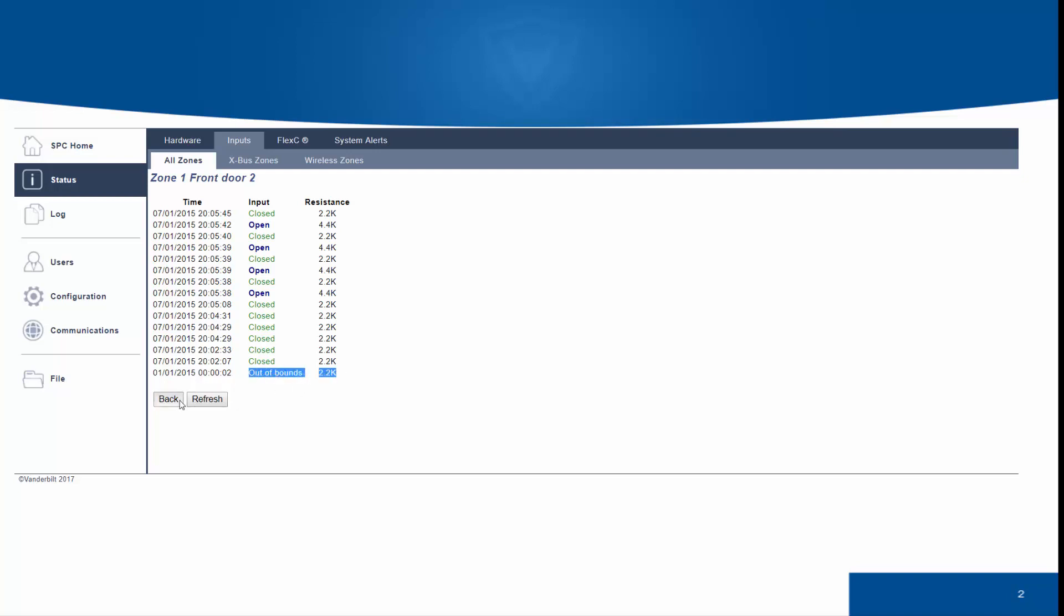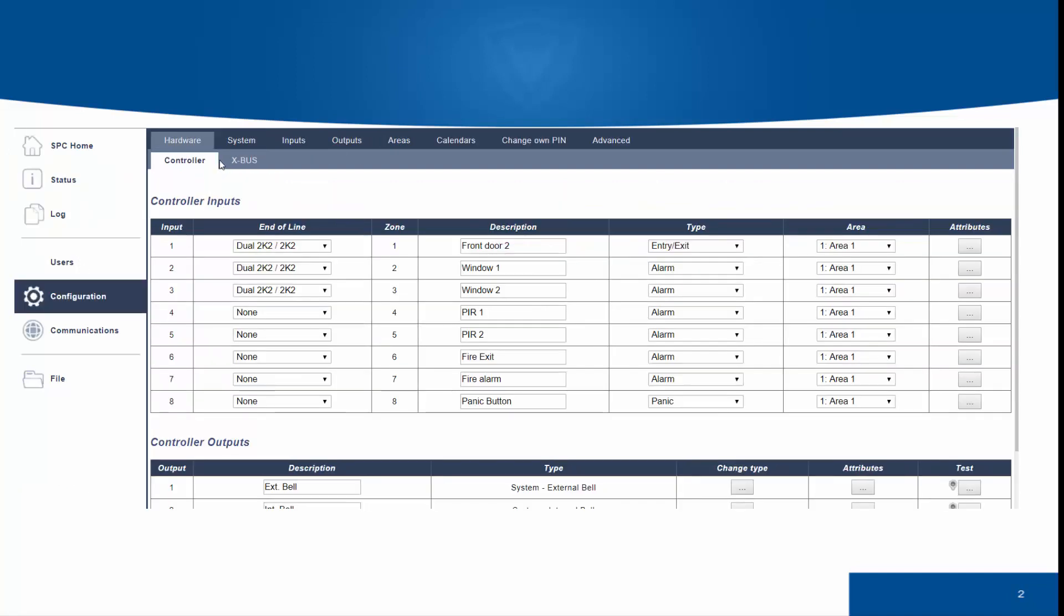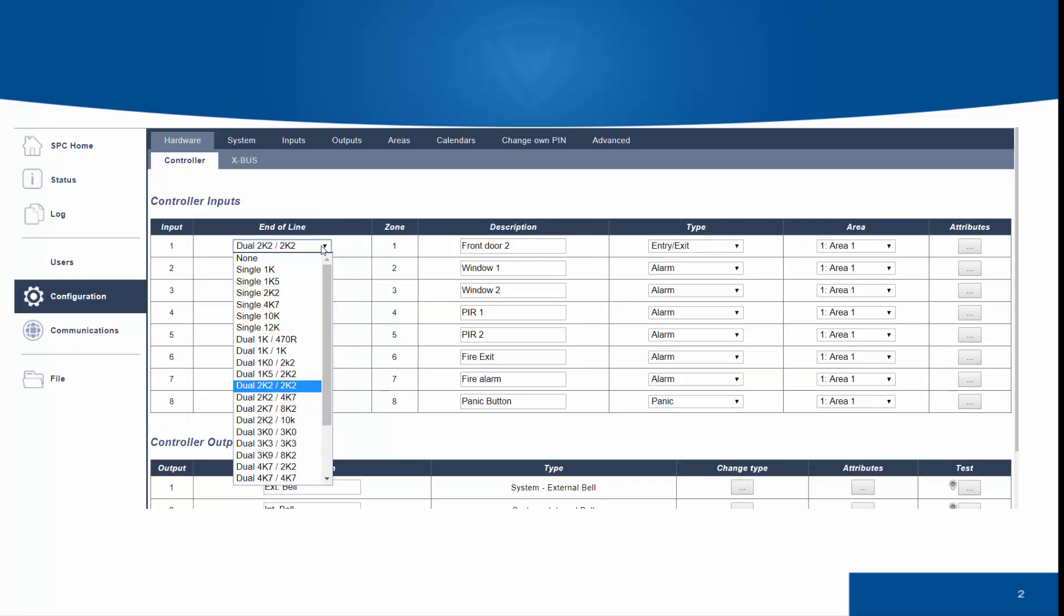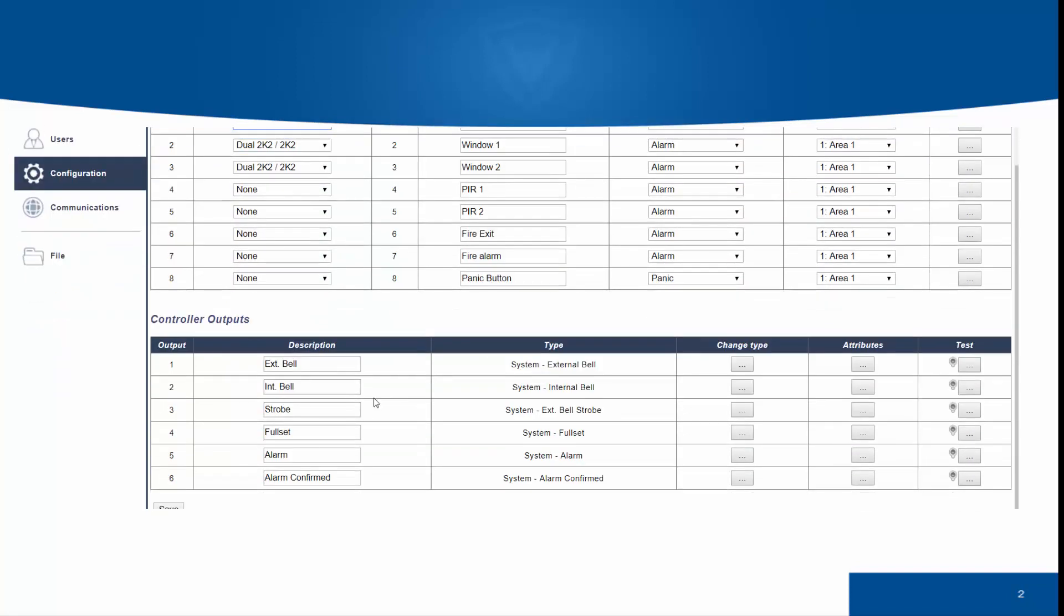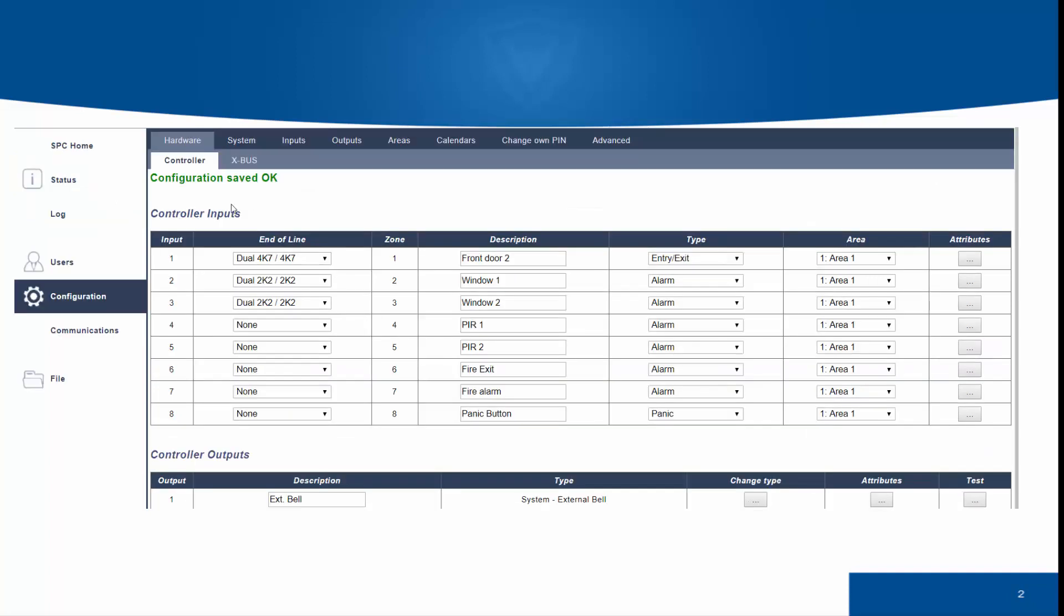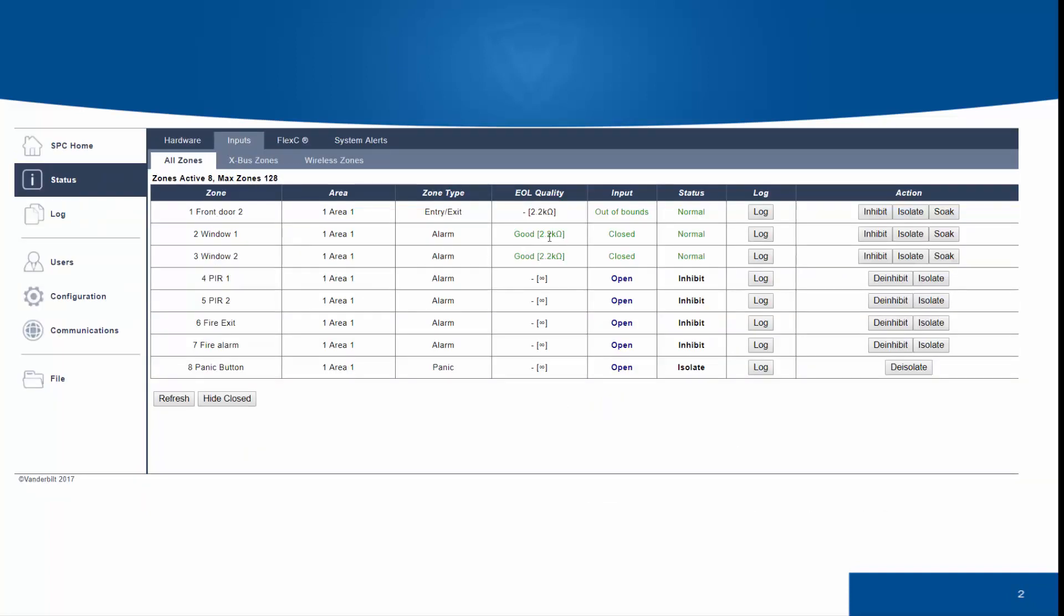You may see an out-of-bounds. An out-of-bounds occurs if the end-of-line selected is not compatible with the configuration option. So, for example, if you had a 4K7 resistor in a 2K2 configuration, this would signal an out-of-bounds. This must be addressed before you leave full engineer mode.